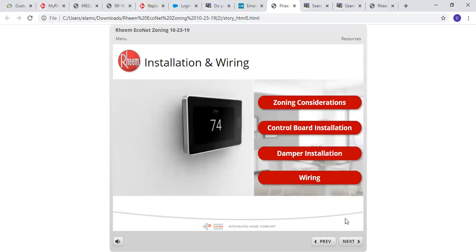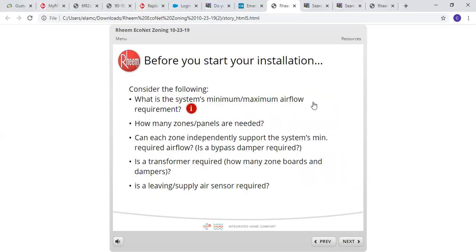Get into some installation and wiring. The big one is zoning considerations. Consider the following. What is the system's minimum and maximum airflow requirement? That is imperative. See the reference section of your furnace or heat pump, so you can determine what your minimum airflow requirement is, and how many zone panels are needed. Can each zone independently support the system's minimum required airflow? That's really important. If each zone can handle the minimum airflow, then you won't need a bypass damper. If you have one that is slightly lower than the minimum airflow, a bypass damper will be required.